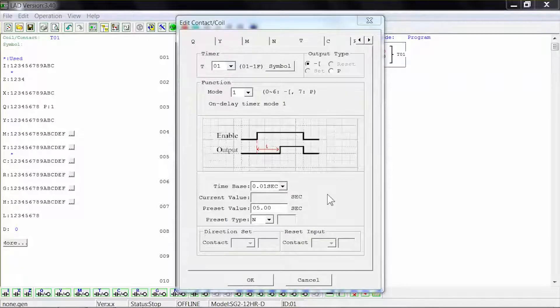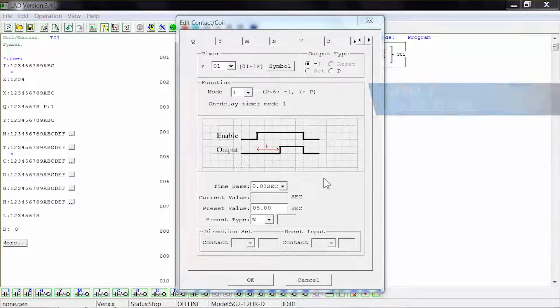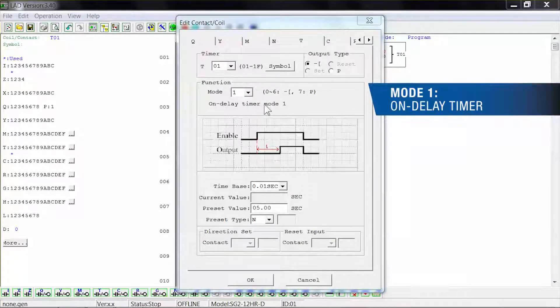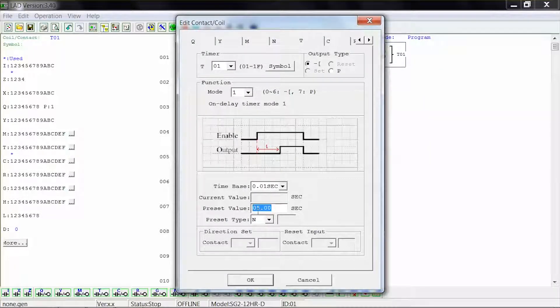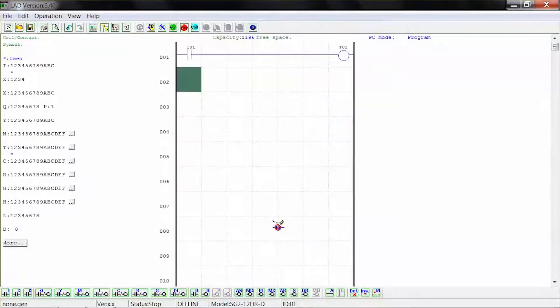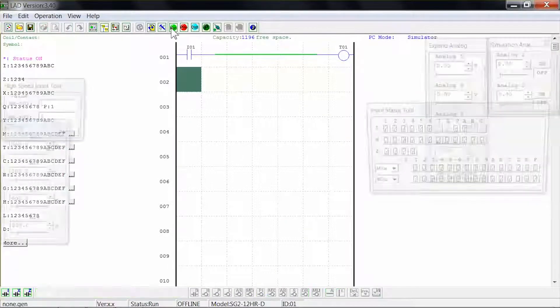For our first example we will use function mode number 1, which is an On Delay timer. Our time base will be .01 seconds and our preset value will be 5 seconds, shown as 5.00. Our preset type is N for numeric constant. Click OK to close the edit coil window and click the green run button to start the simulation.